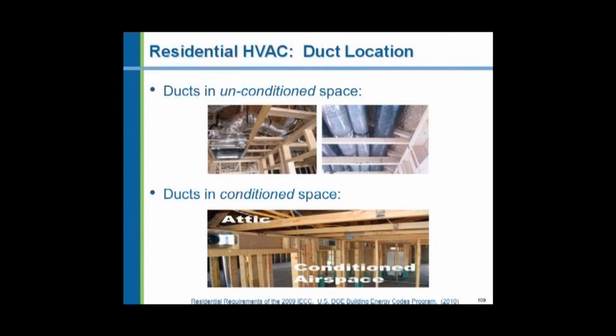It will be after the ceiling board is put in. And the lower picture is installed above a corridor below an insulated ceiling. I, as a professional engineer, would not design in this manner, however. Remember, the codes are minimum construction. They outline the worst building that you can legally build.